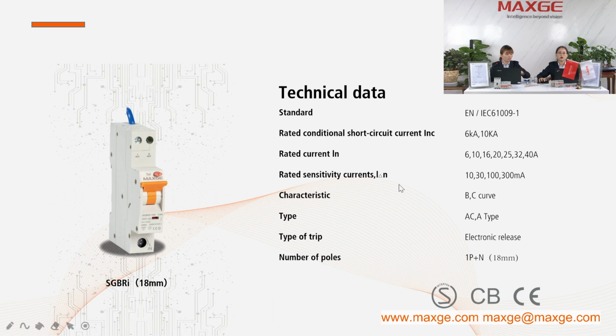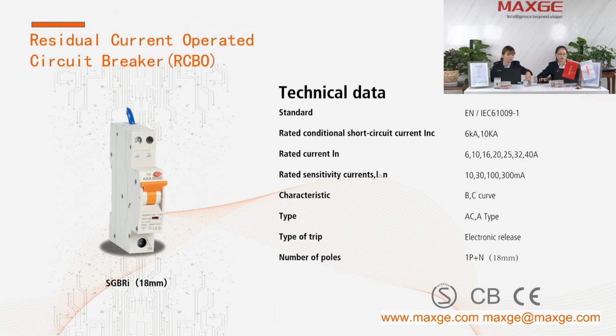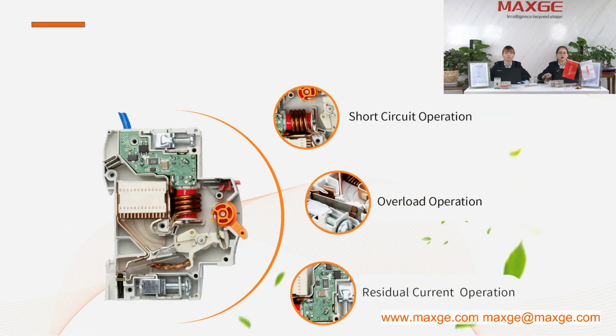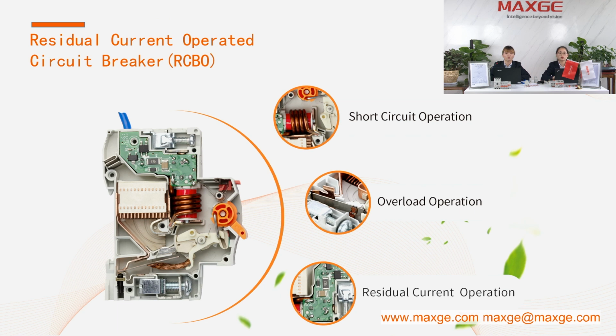Next, I will introduce the RCBO with model name SGBRI. The rated current is from 6 ampere to 40 ampere. With B and C curve, the rated sensitivity current is 10, 30, 100, 300 mA. It has AC type and A type. We only have electronic type for this RCBO. It has small size, the same as a 1 pole MCB. Here we will show you our RCBO. It has an MCB coil magnetic part for short circuit operation, an MCB bimetal part for overload operation, and the additional PCB and transformer part for residual current operation.